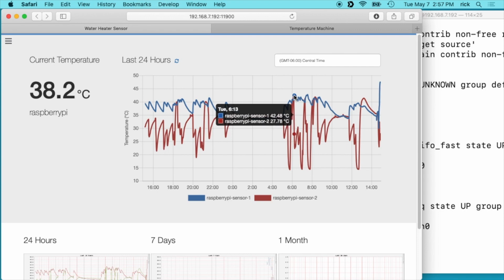So what probably happened there is that you shut the shower off, and the water heater is still heating, and it doesn't have a place for that heat to go, so it goes back up the cold side. So you can see the cold got about as hot as the hot side, and then the cold dropped back down here. And you can see that this is probably someone taking a shower and then turning the shower off. Someone taking a shower, turning the shower off.